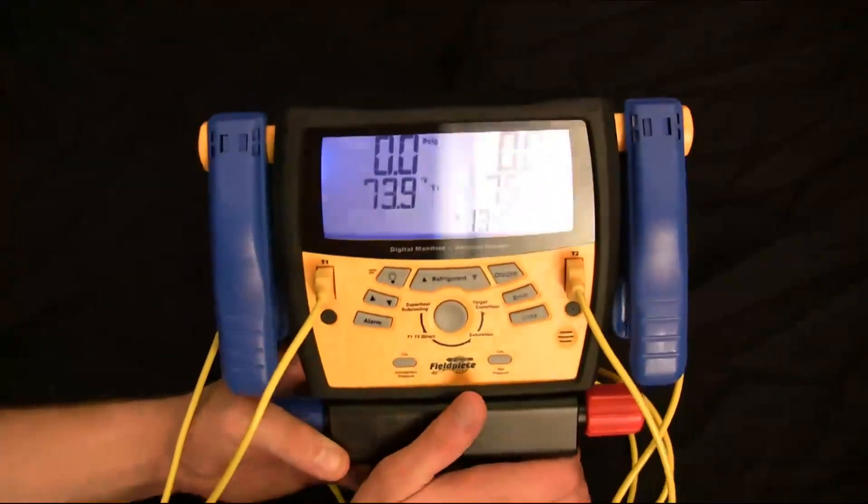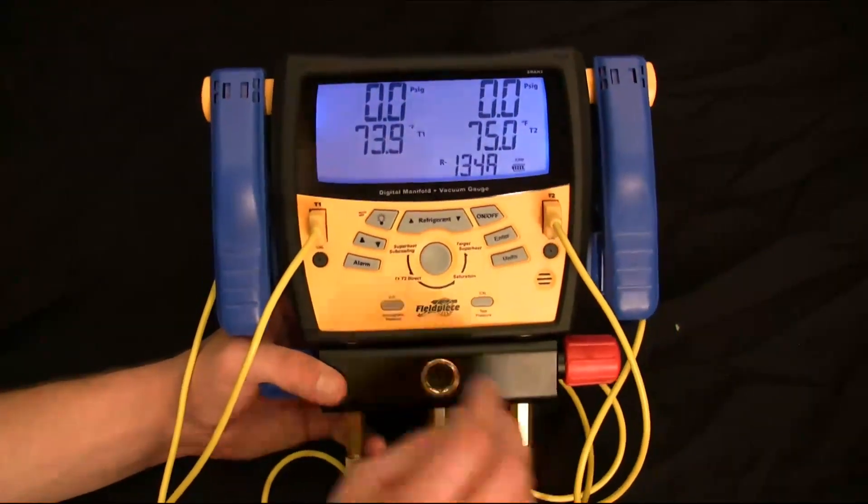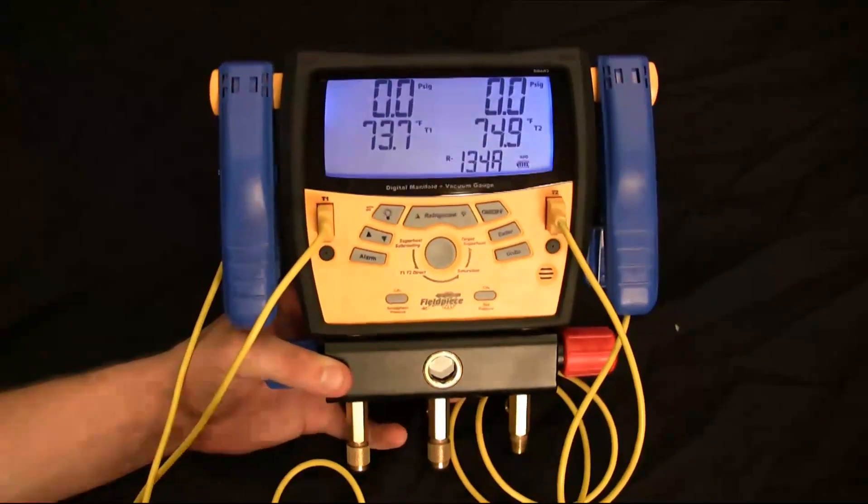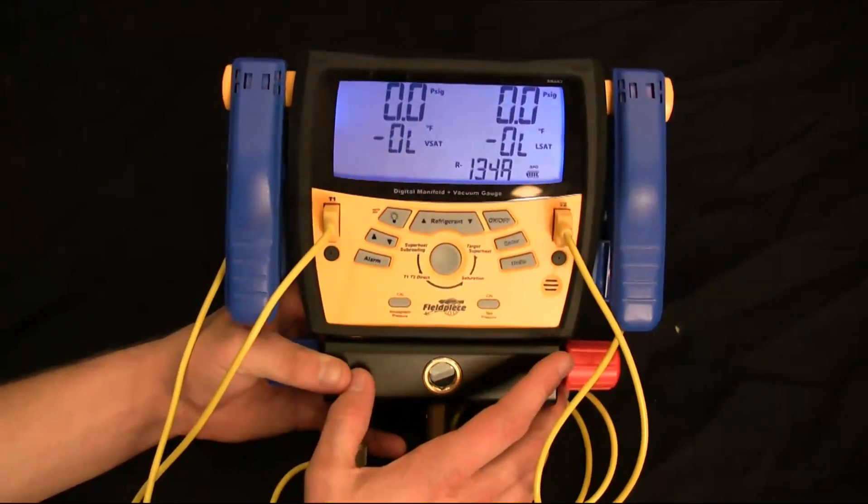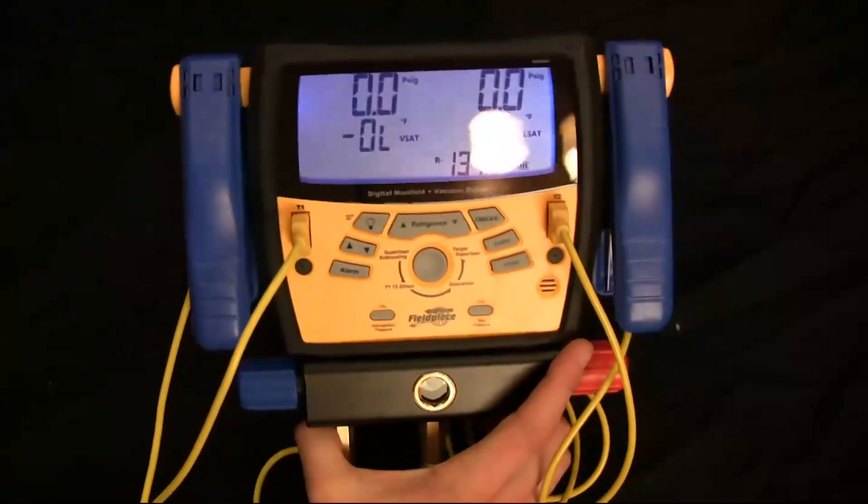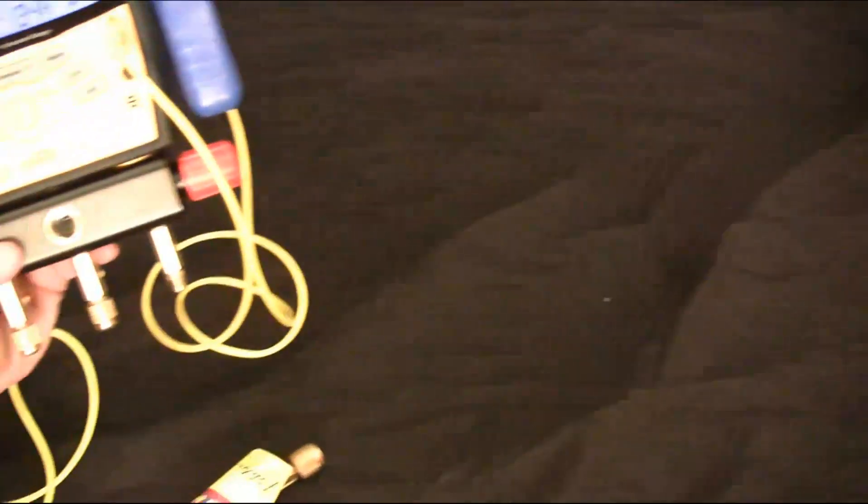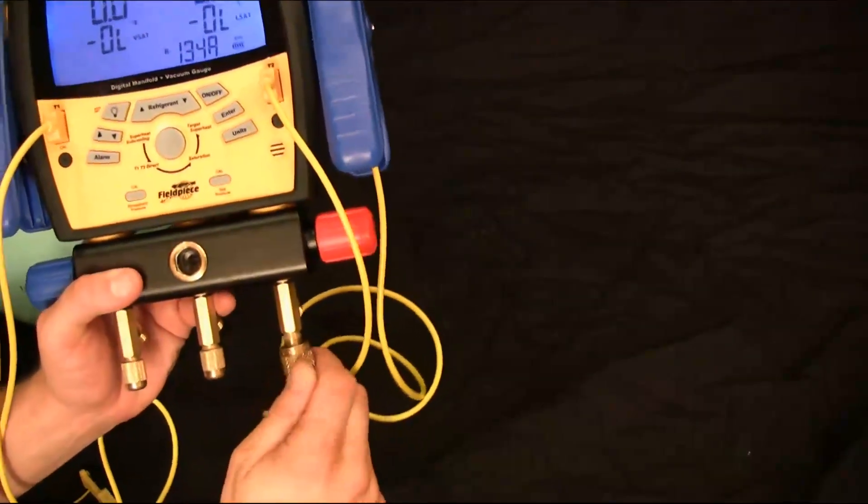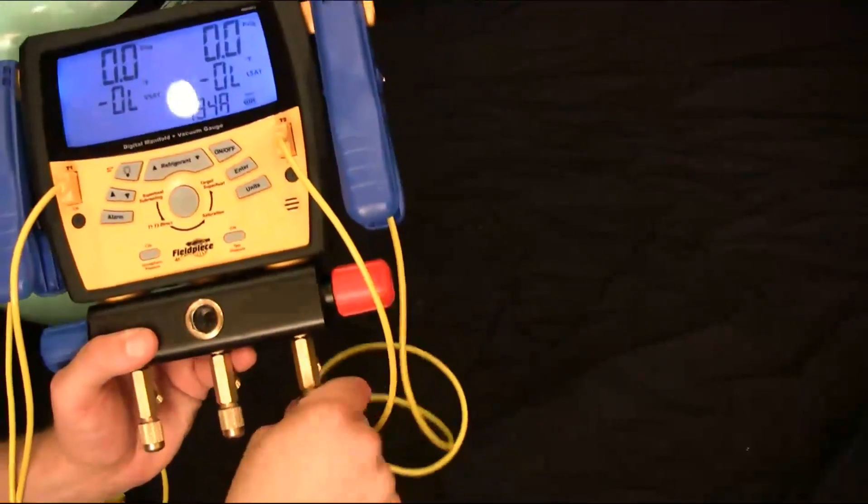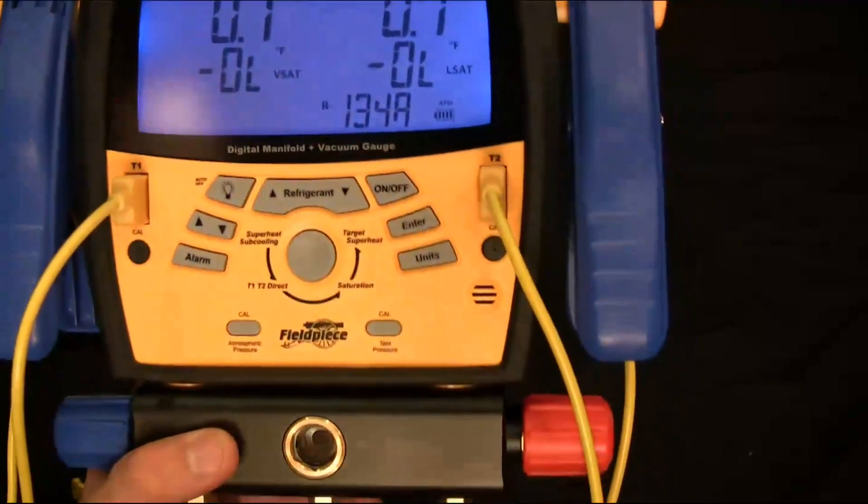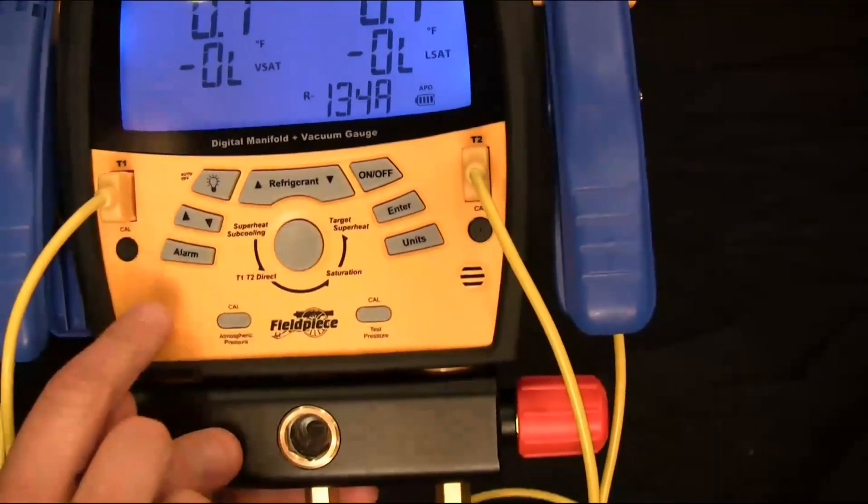So the manifold also comes with wet and dry bulb thermocouples that you could plug into these ports and use them for taking your wet and dry bulbs. All right. So next mode is your vapor saturation temperature mode. If I hook this up to a bottle of refrigerant, I have a bottle of 134A right over here. And I'm just going to hook it up. And I do have my refrigerant set for 134.